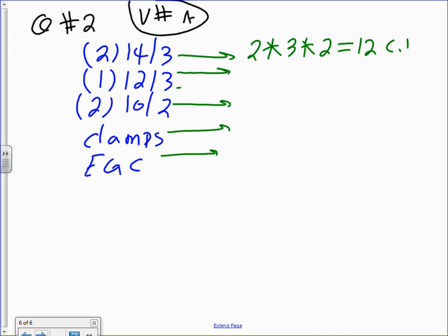One more time. The first number here, Karen, is for the number of cables, because I have 2 cables. The second number is the 3, because of the 3 conductors. And the third number is 2. This is the cubic inch allowance for number 14. Cool? And all this stuff that we're using is from 314.16 A and B. These are all information. Okay, the rest is history, so I'm going to go directly and start putting in.